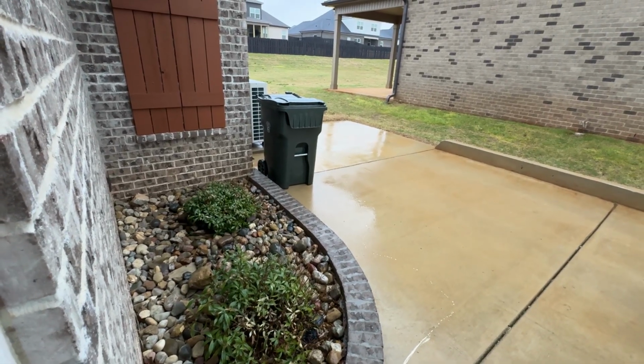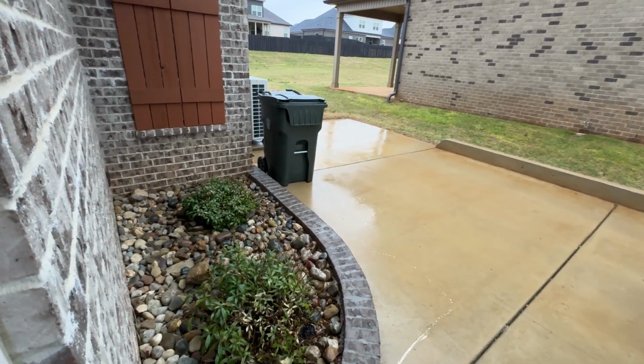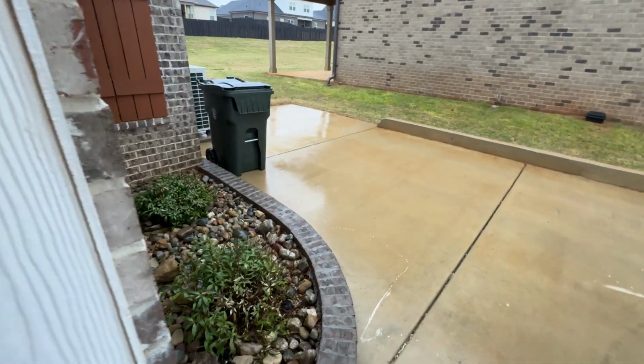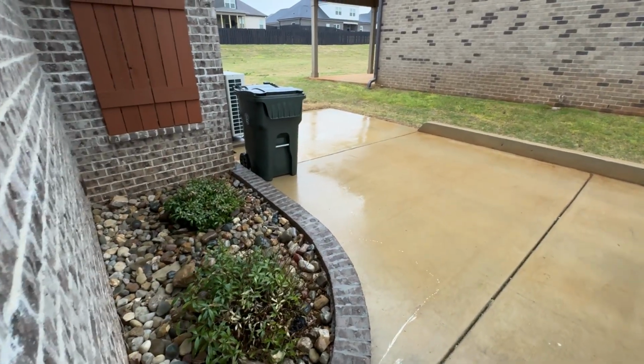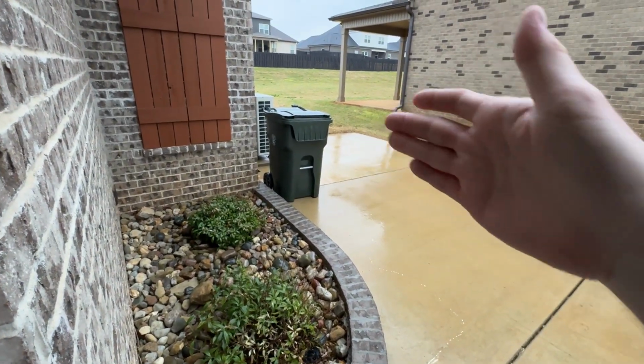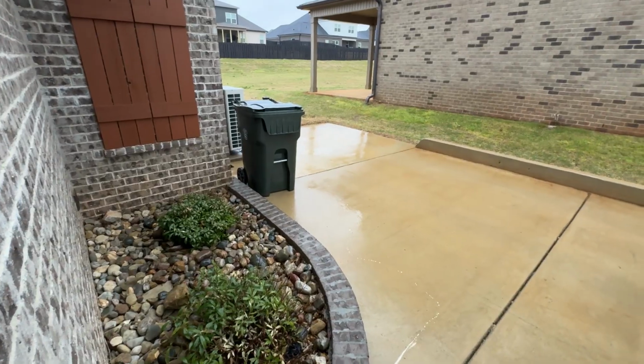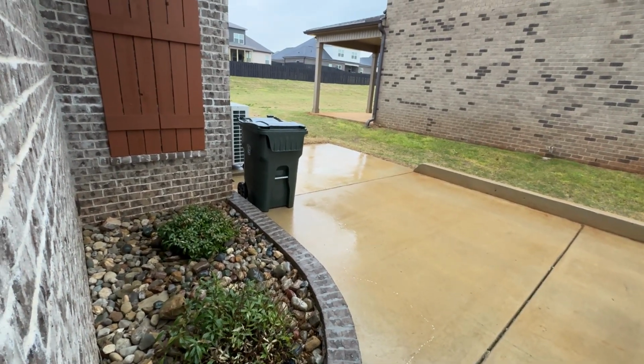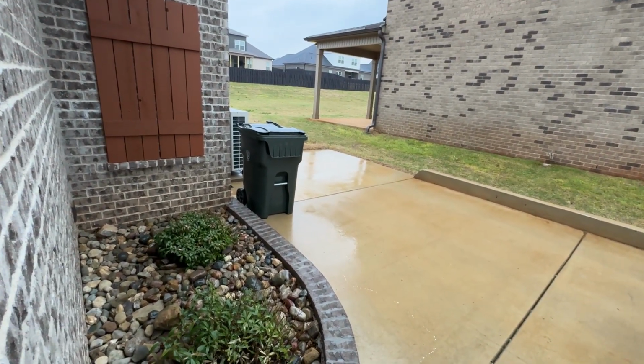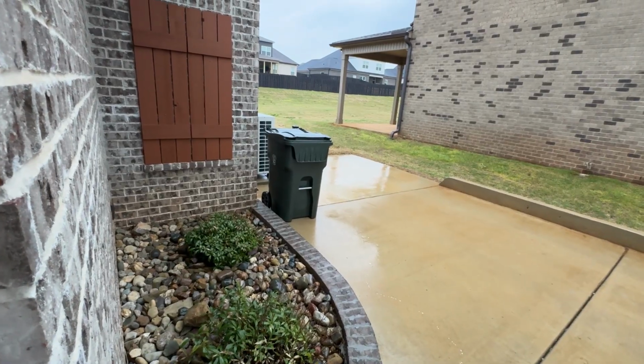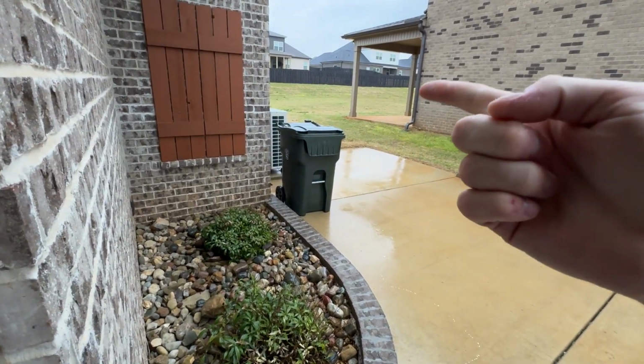The first time I called Huntsville Utilities, they sent a crew out. It was yesterday morning. Conditioned Air was also here, just to recalibrate it and make sure that everything was good, which it was. But the crew came out and they tested at my meter base. They tested the transformer box in my front yard, and they tested here at the meter.